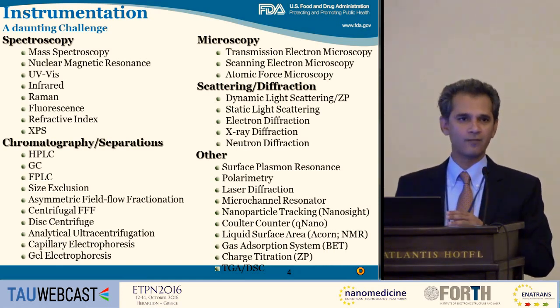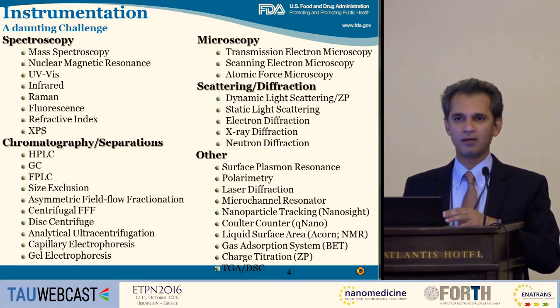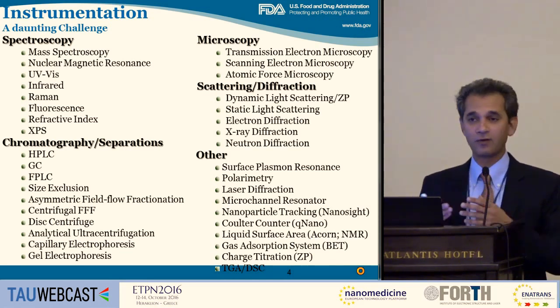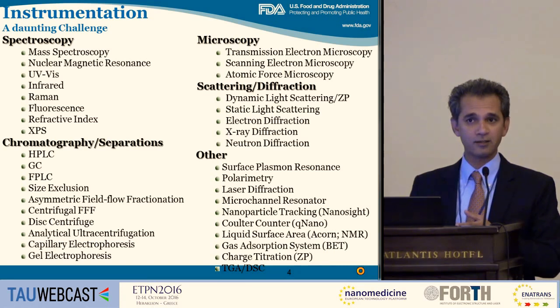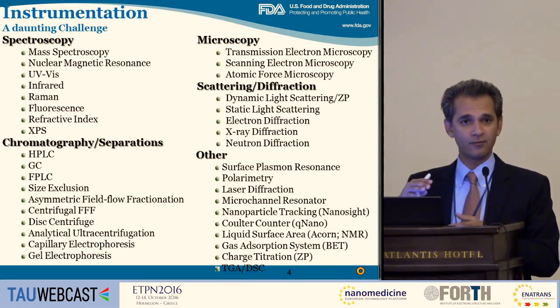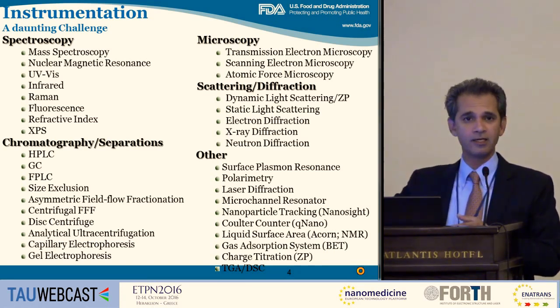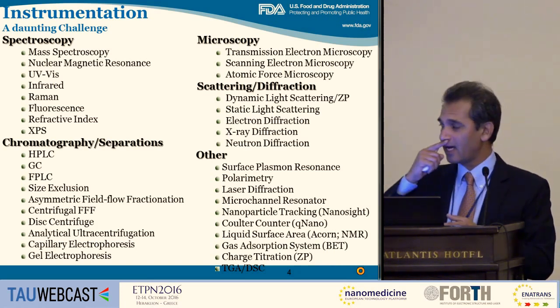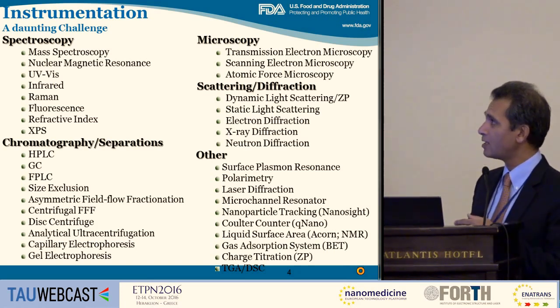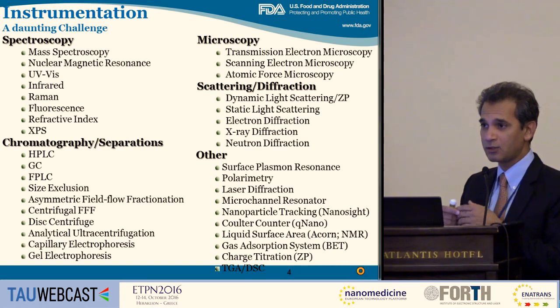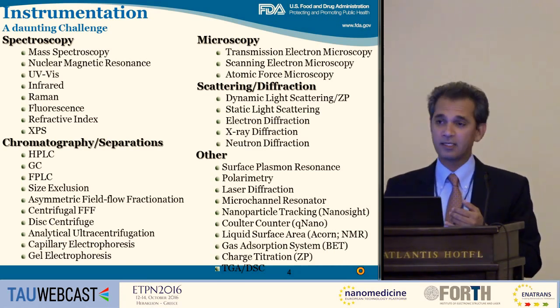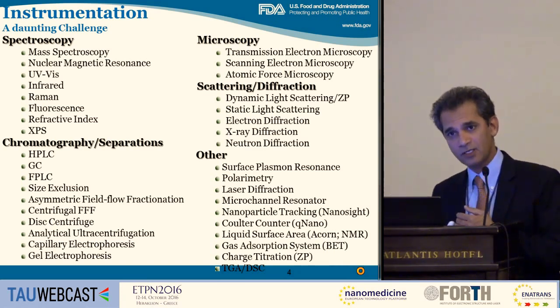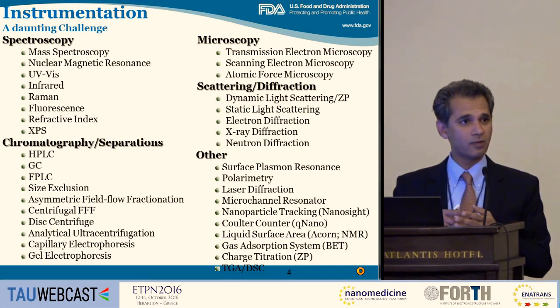So that's where you have to go through a fractionation method such as field flow fractionation, size exclusion chromatography, and other kinds of methods to look at the polydispersity in the sample. And depending on how you measure, it is not only that the instrument spits out a number, but it depends on whether you are looking at the Z average, the intensity, the volume, or the number.